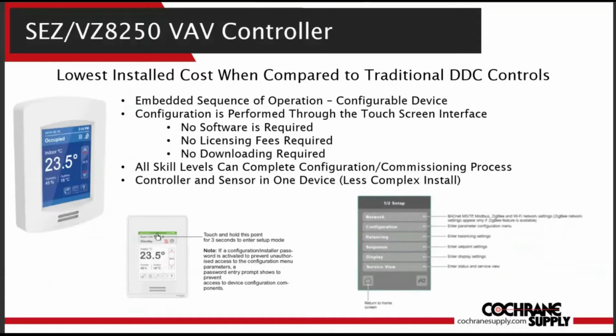8250 series room controllers are configurable devices. They have an embedded sequence of operations that are tailored for VAV and VVT control applications. Configuring the device is done through the touchscreen interface, so there's no software required, there's no licensing fees, and there's no downloading required. It's ready to use out of the box.